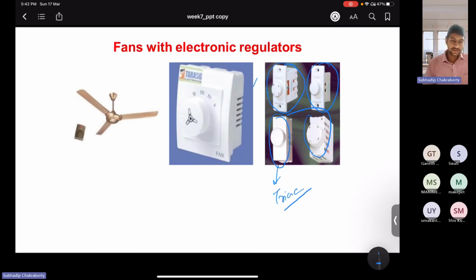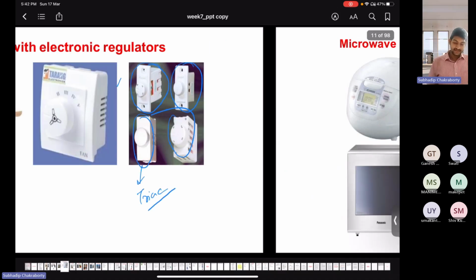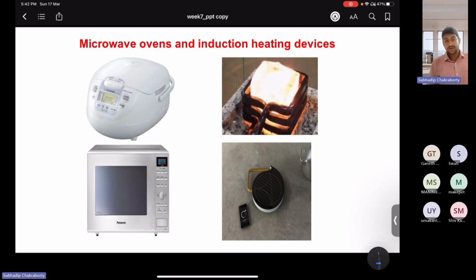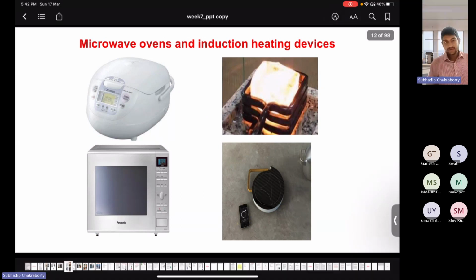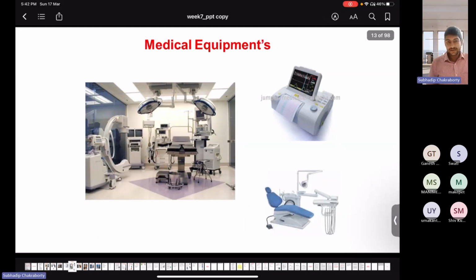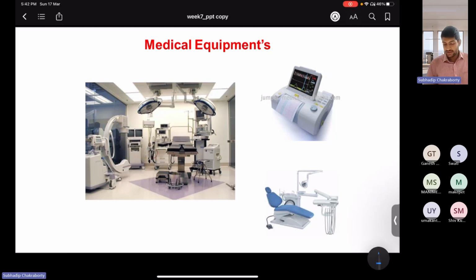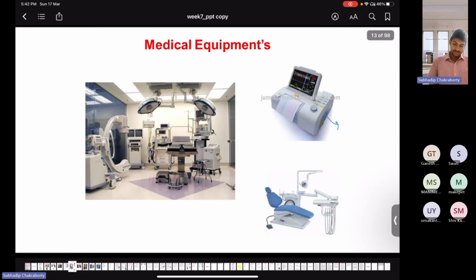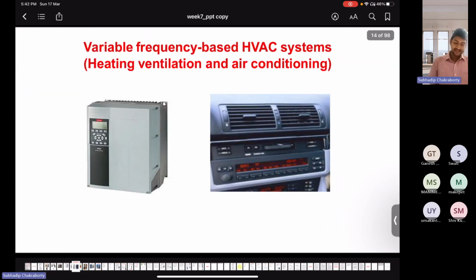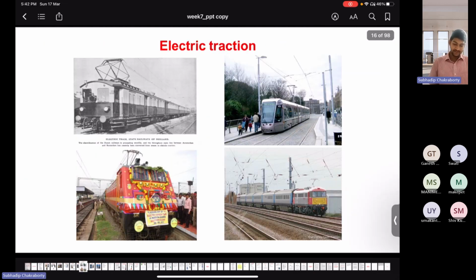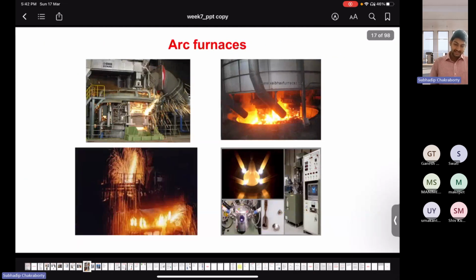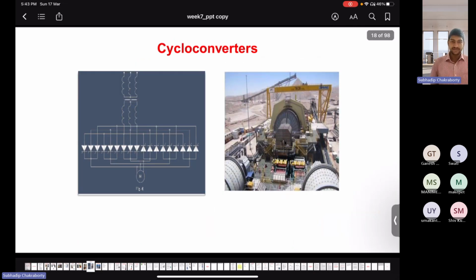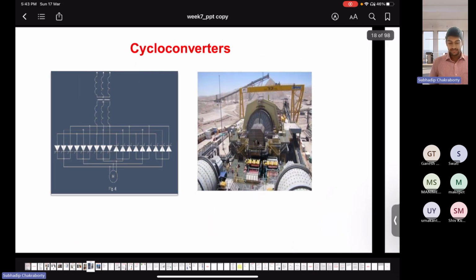You want to minimize the voltage drop and increase the efficiency for this given rating, right? So we use triacs, but they are all non-linear elements. Okay, they will lead to non-linear nature of the currents. So the medical equipment also is dominated with electronic loads, controllers, and sensors, which will lead to DC offsets and non-linearities in the currents. Basically, the current-based quality problems are predominant in day-to-day practical applications, as you can see. All the electronic loads, your mobile charger and all those applications are non-linear.